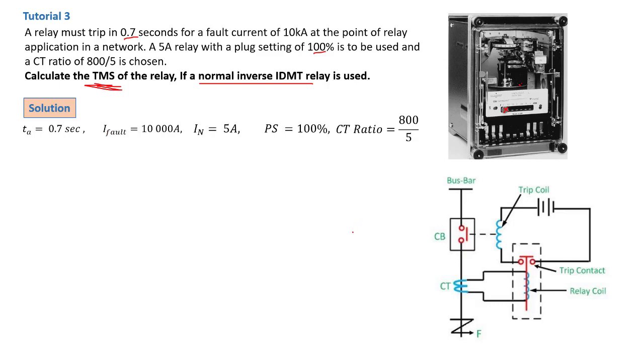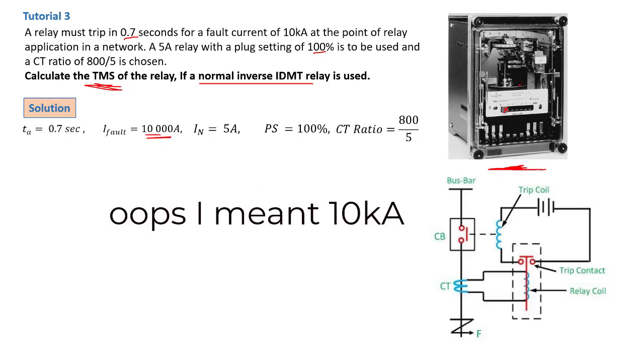An IDMT relay — Inverse Definite Minimum Time relay — is what you see here on screen. It is inverse precisely because it operates in a counter direction with the current regarding timing. When the fault current stands at 10 kilo-amps, the relay must trip faster — here that is 0.7 seconds, which is extremely fast.